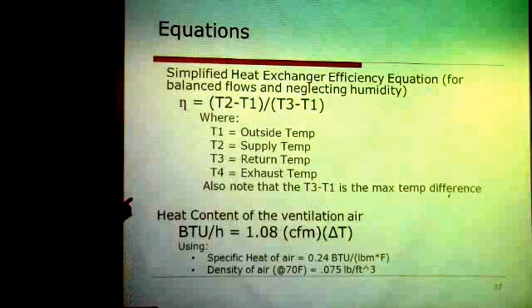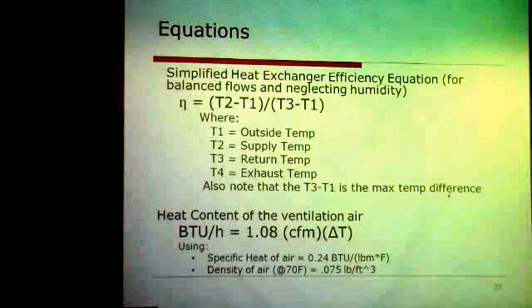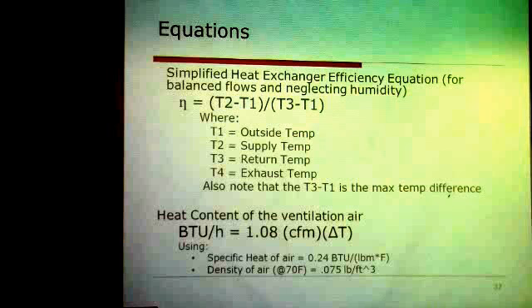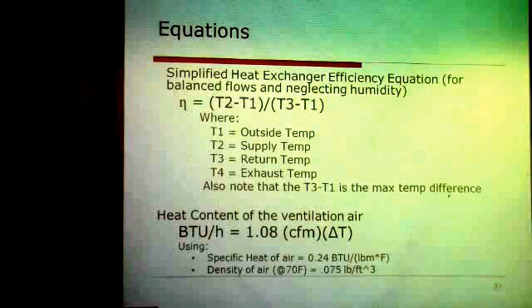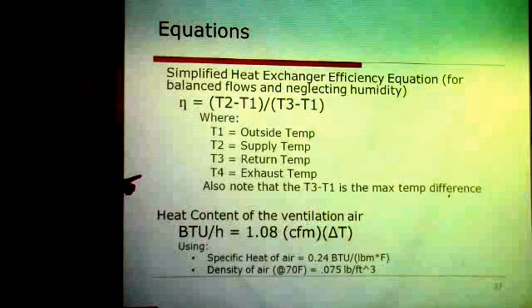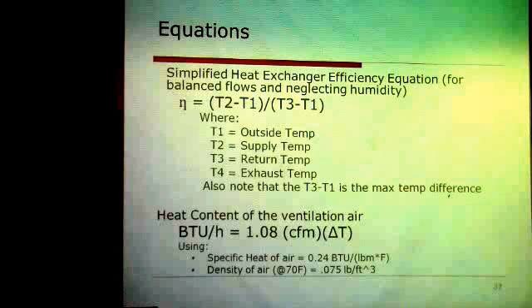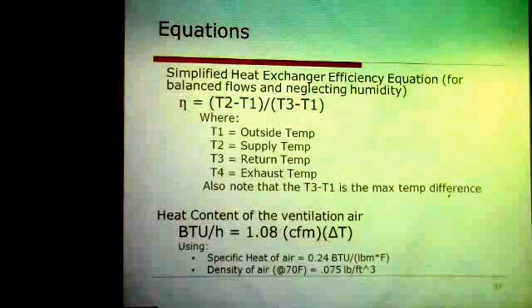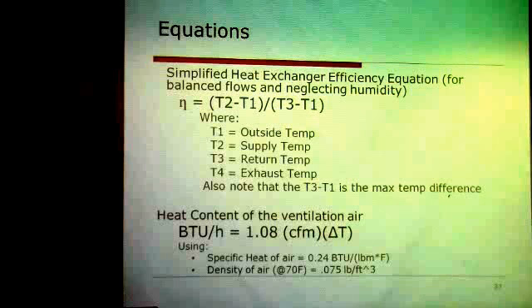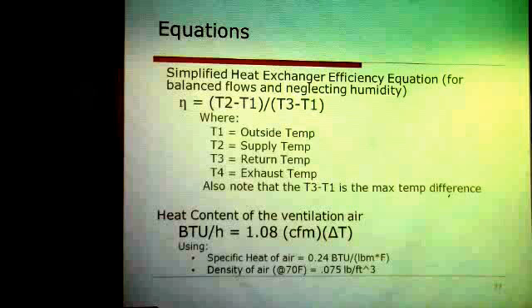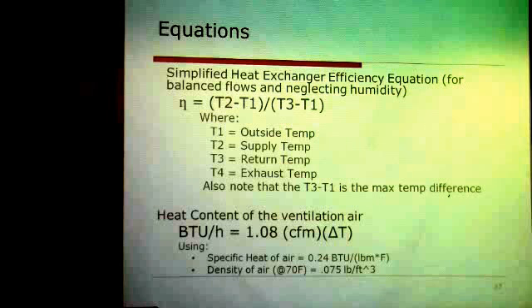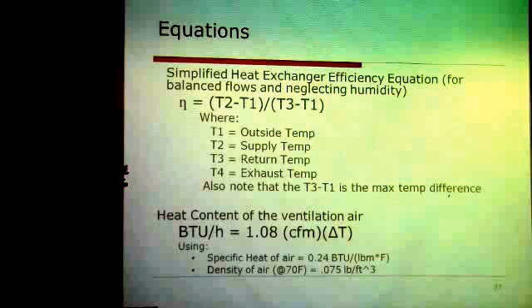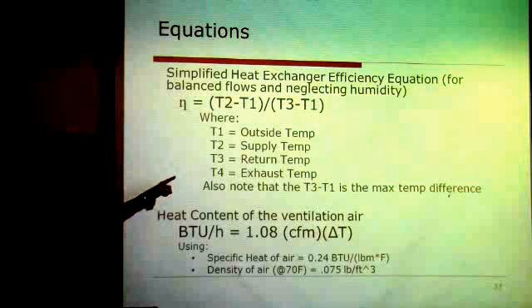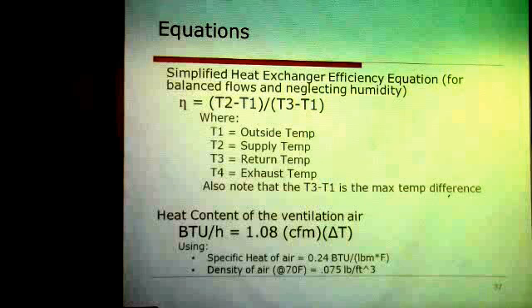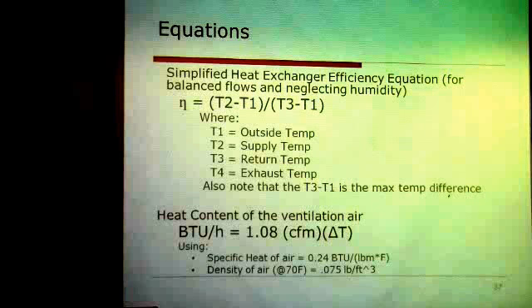Just a quick efficiency equation. This is actually assuming both flows are balanced. We try to keep both flows balanced. So if you do that, and neglecting humidity. So of course, if you have humidity, like on the East Coast a lot, if you're trying to cool the air, most of your cooling doesn't decrease the air temperature, but it will cool the humidity and maybe condense it out. So you can't use this. But this is just a very simplified efficiency equation where you're taking T2 minus T1, the supply temperature minus the outside temperature. So that's the air.